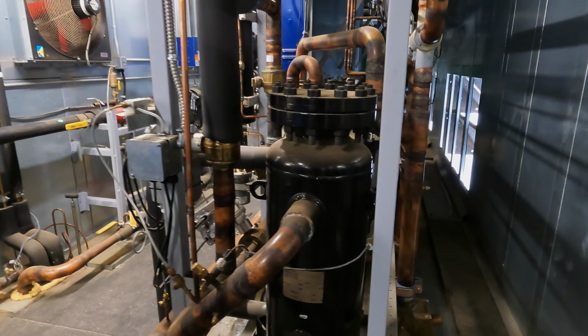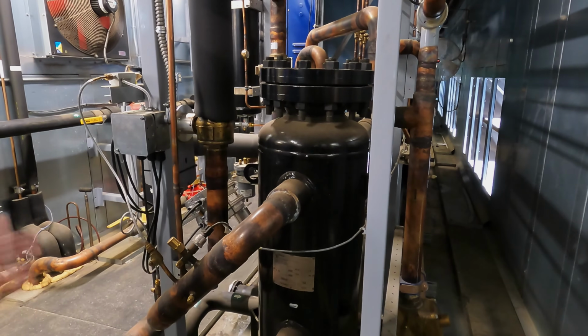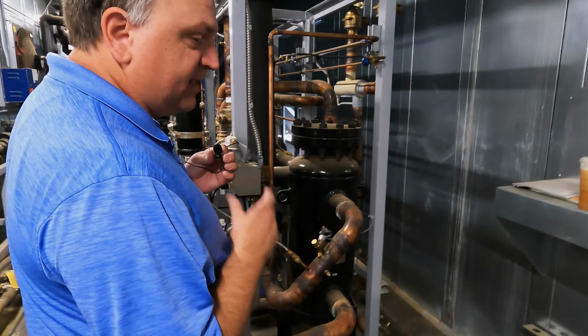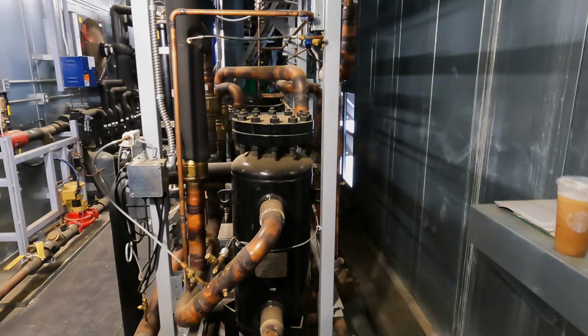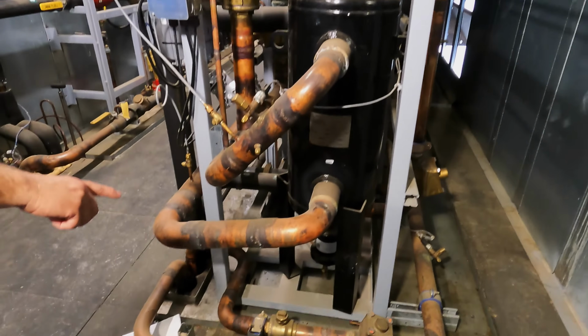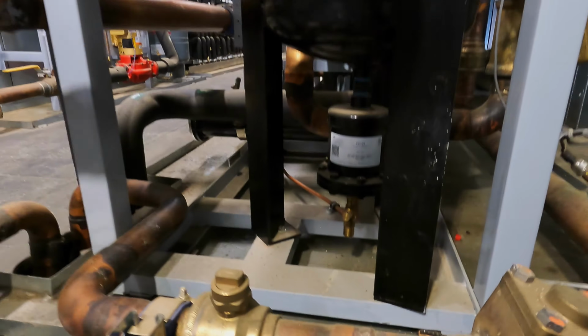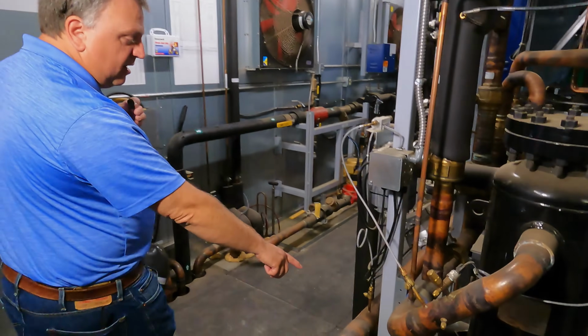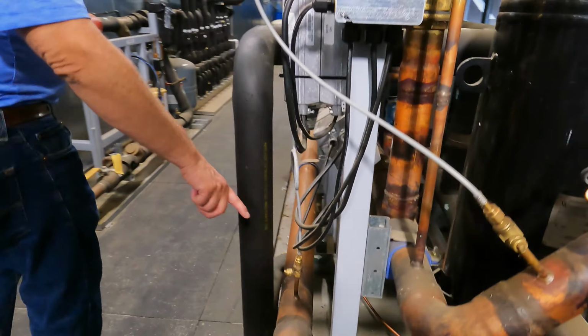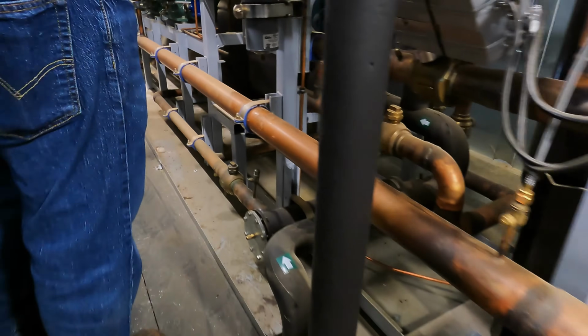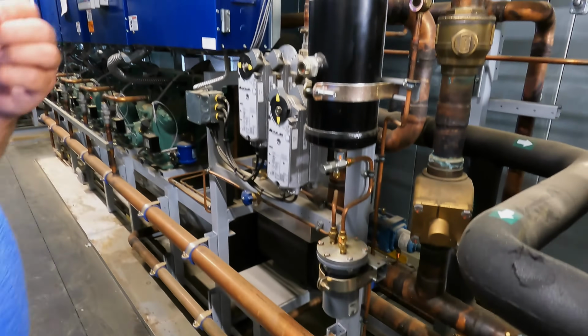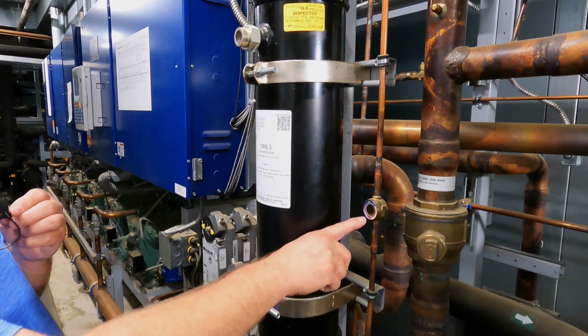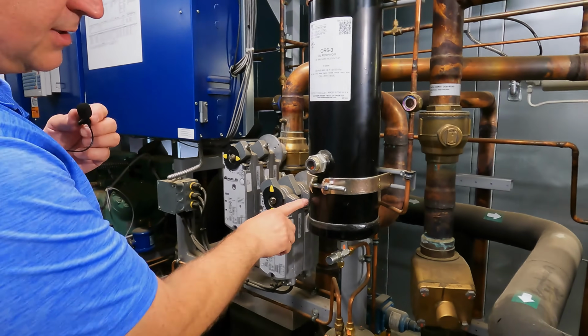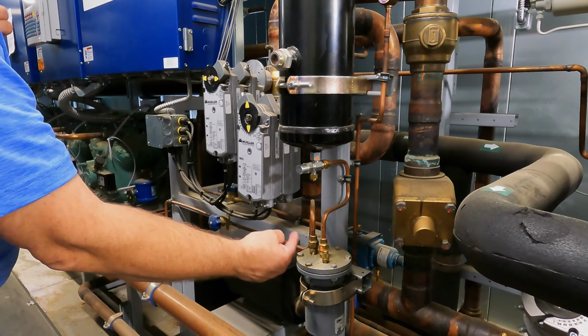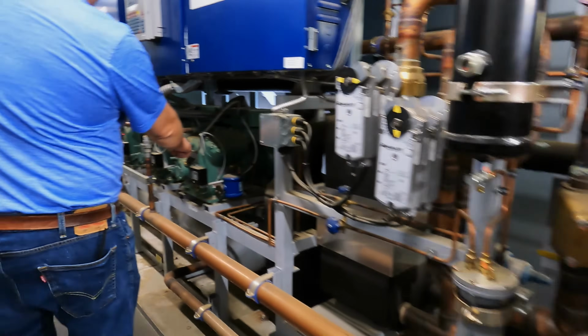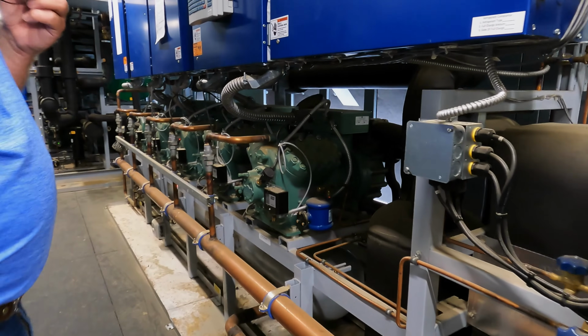This particular one is a coalescent filtered style. It has a coalescent filter. It squeezes the oil out of the refrigerant, and then it's going to drop that oil at the very bottom to our oil float. And it's going to push all that oil that it caught back up through this line and into our oil reservoir. And as you can see, the oil's coming up through here. Once it's in our oil reservoir, it's going to come down to an oil filter, go back over, and feed back into our compressors through our oil pipe.